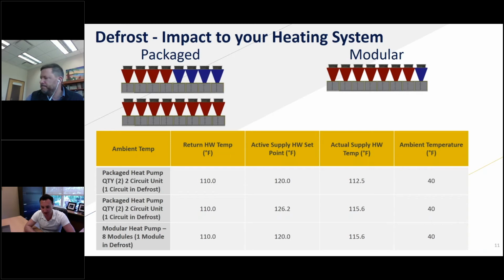So just to add on to that a little, during, for example, a snow day or a snowstorm, when snowflakes are in contact with the coil, will longer defrost be needed, and what would the energy impact be? Ballpark. It's hard to ballpark an energy efficiency impact because it really is going to come down to how much of the machine we're running and the specific ambient temperature, which is driving how much ice we're forming. So yes, if it is snowing, we're going to have a lot of moisture in the air. I would say your coils are going to frost sooner than if it wasn't snowing. So in those situations, you would be defrosting more of the time than if it was colder and drier. But it's really something you've got to look at on a case by case basis.